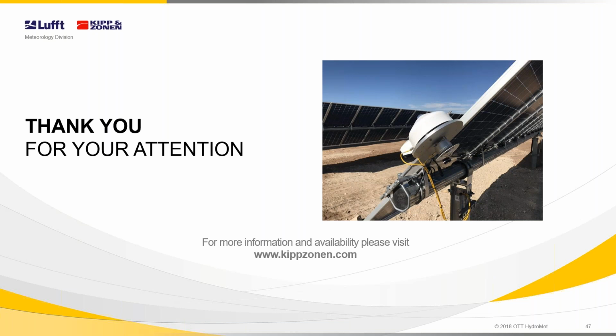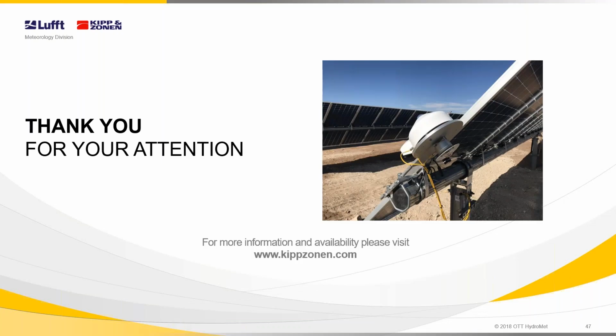Okay, as I understand this, the question is how many albedo meters are required. This is prescribed in the IEC 61724-1, and it depends on the size of the plant. So if you have a plant which is larger, then more albedo meters are required than if you have a plant which is smaller.